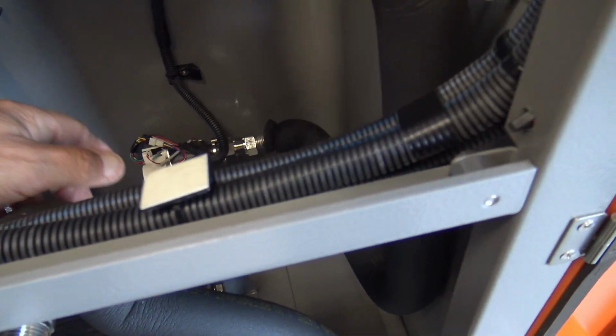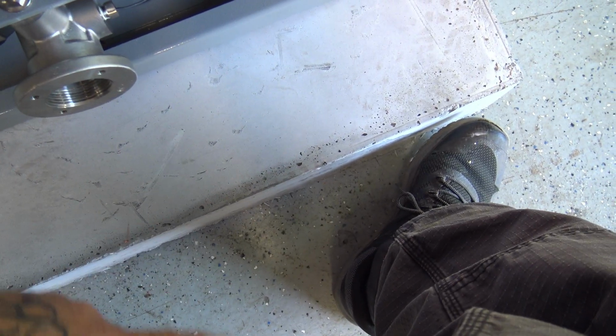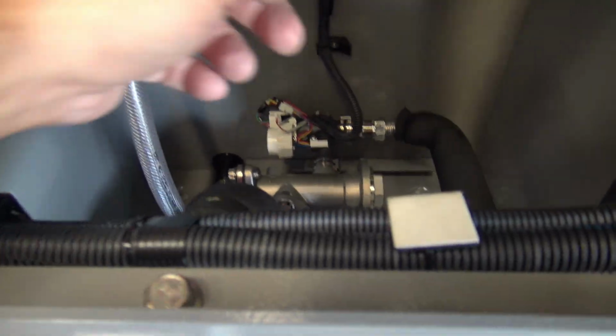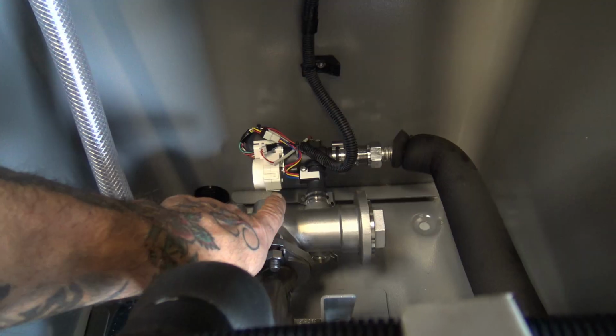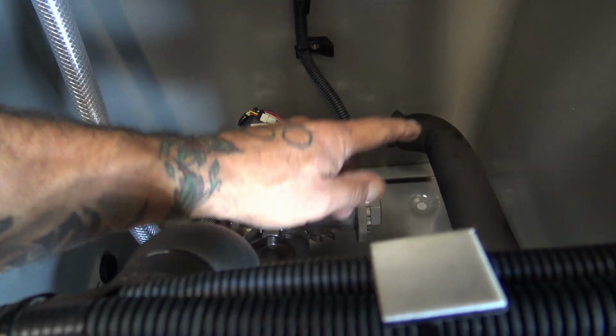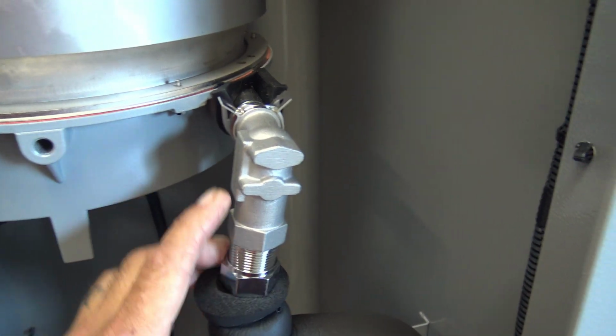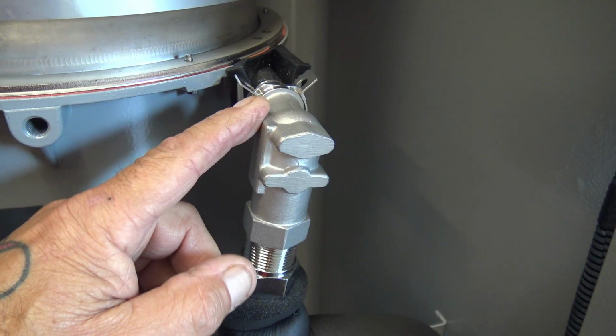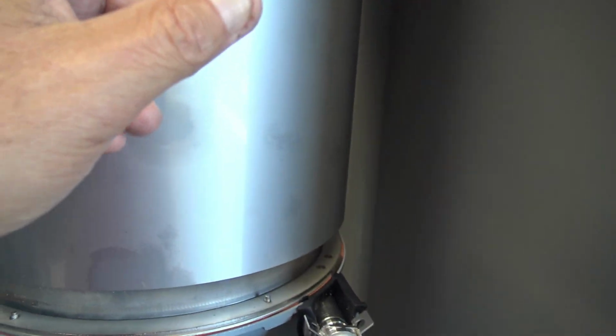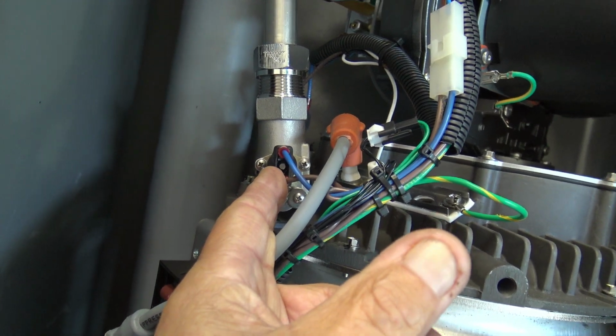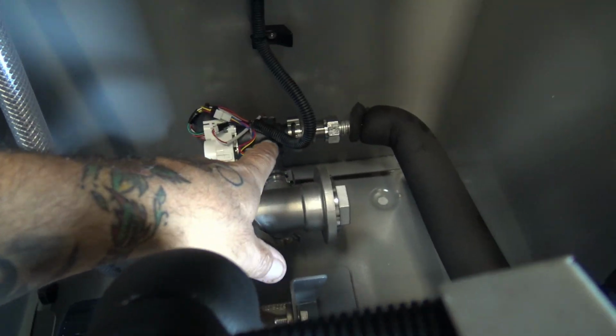Now, draining out the pipe - even if you had a drain on this, you're still not going to get water out from here, because water won't come back down this way. Remember, the cold water goes in through the bottom inlet fitting, through the heat exchanger, gets heated up, comes out the top water valve fitting, and then goes to the system. So you're not going to get water out this way.